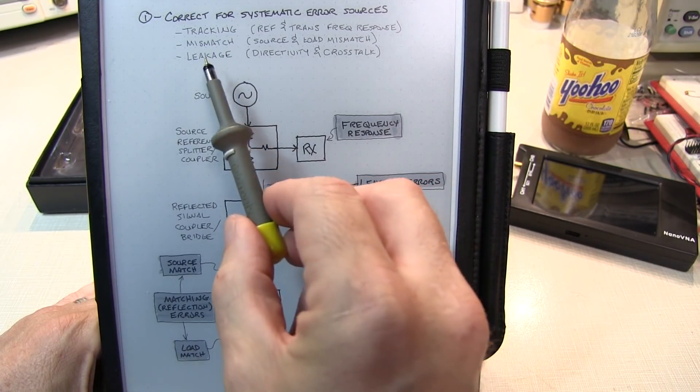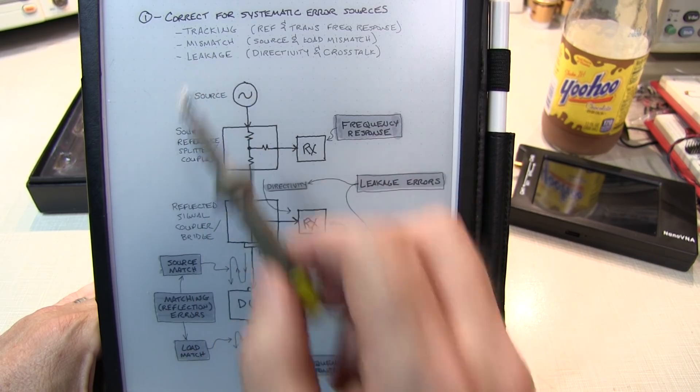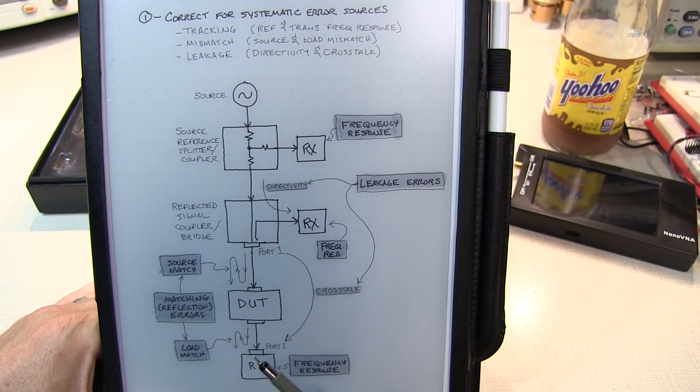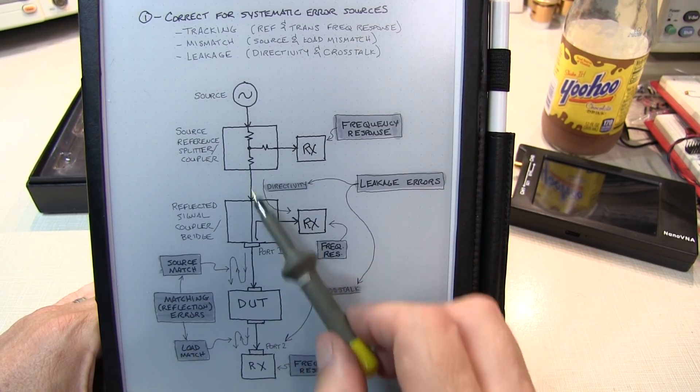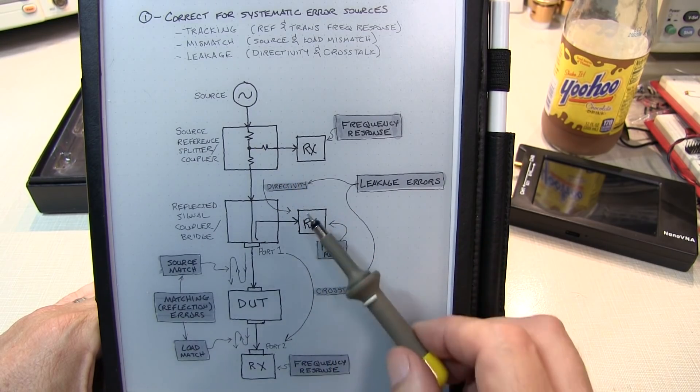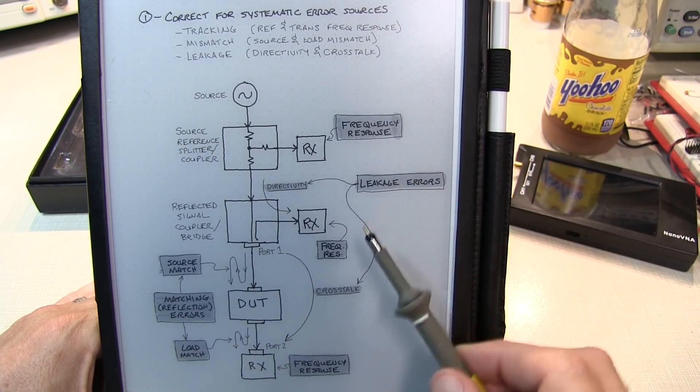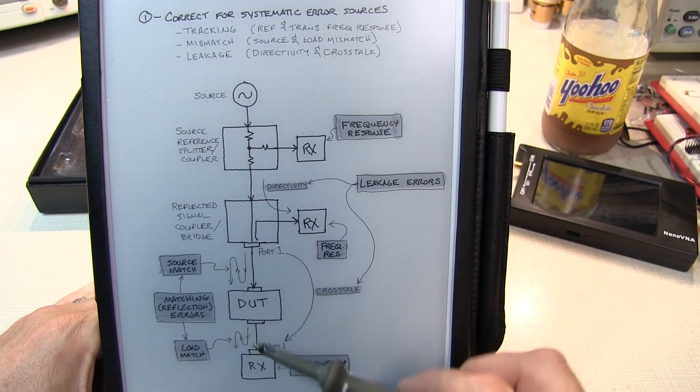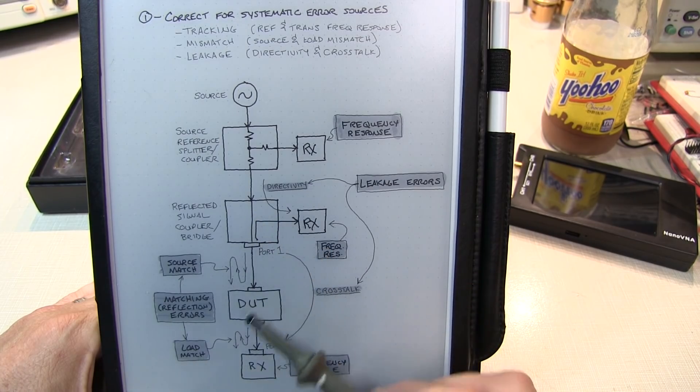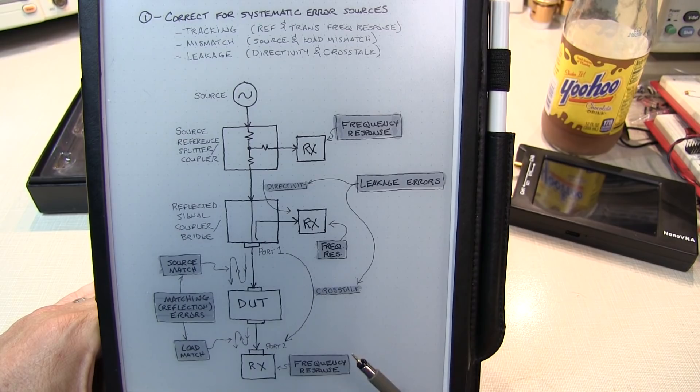Now a third class of errors we need to correct for are leakage errors. And these are unintended RF paths. For example, they may be related to the directivity of the directional coupler. Now ideally the directional coupler is only going to couple energy coming in the reverse direction, but there will be some leakage in the forward direction. And of course, we want to eliminate the effect of that leakage path going to the port 1 receiver. Another is crosstalk. Crosstalk is coupling between the two ports of the VNA, which is essentially a path for RF to go around and bypass the DUT. And of course, we want to be able to correct for and remove that so we can only measure what's going on in the DUT.